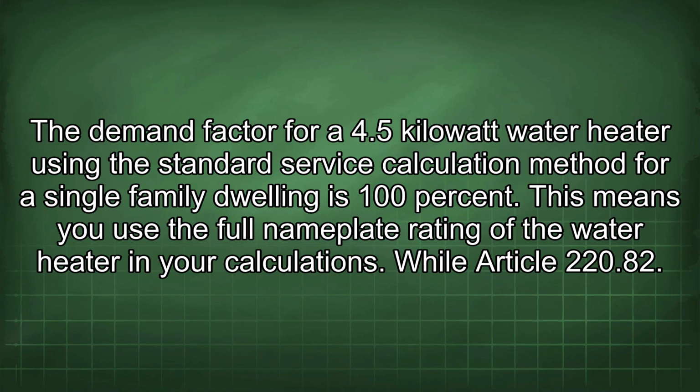A demand factor for a 4.5 kilowatt water heater using the standard service calculation method for a single-family dwelling is 100%. This means you use the full nameplate rating of the water heater in your calculations.